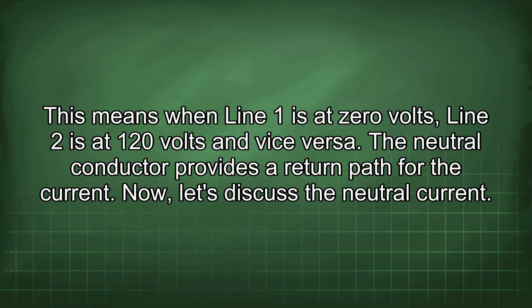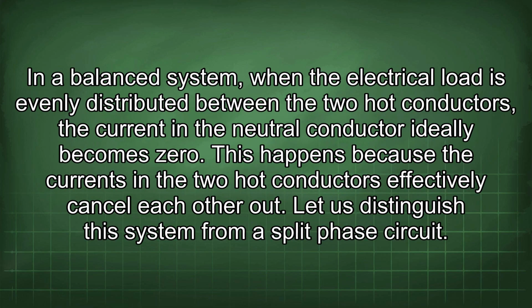Now let's discuss the neutral current. In a balanced system, when the electrical load is evenly distributed between the 2 hot conductors, the current in the neutral conductor ideally becomes 0. This happens because the currents in the 2 hot conductors effectively cancel each other out.